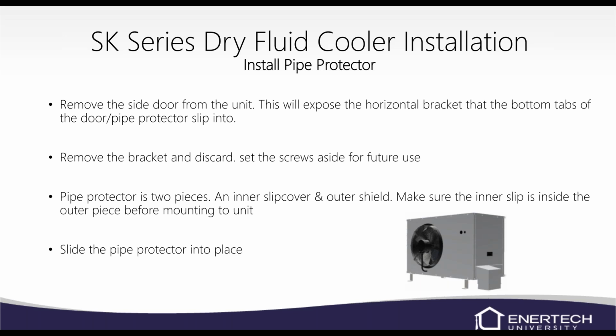Obviously, you've got to put your water lines on there first before you put the pipe protector on. You can remove the bracket that's there and disregard it, but save the screws for when you put the pipe protector back on. It is 2 pieces. There's an inner slip cover and an outer shield. Make sure the inner slip is inside the outer piece before mounting it to the unit. And then basically it's going to slide into place over your pipe and protect it from getting hit by a trimmer or a lawnmower, or something like that. Dog chewing on it, who knows.